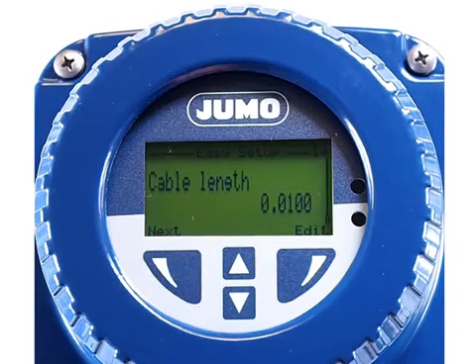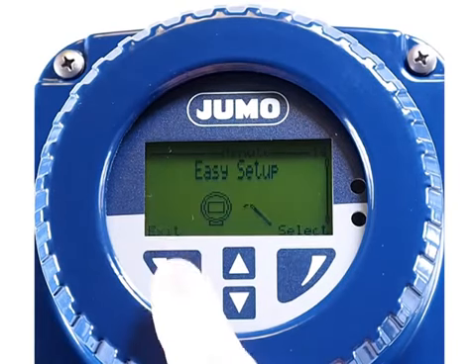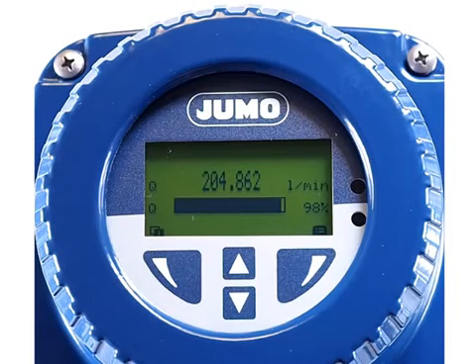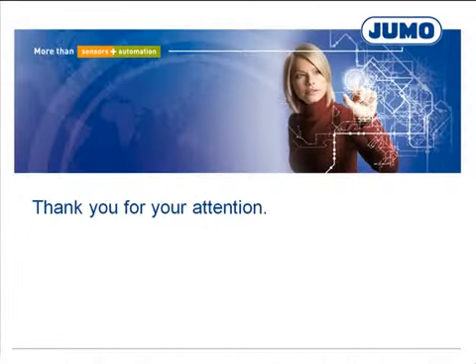At last, the signal cable length is set. This is necessary if the transmitter is separated from the sensor. In our case, transmitter and sensor are fixedly connected. The standard value for the cable length is 0.01 meter. Thereafter, the basic steps necessary for commissioning have been processed and the device is ready to measure.